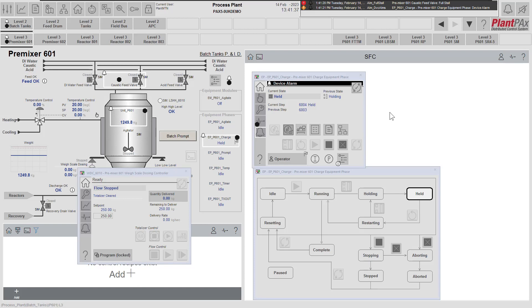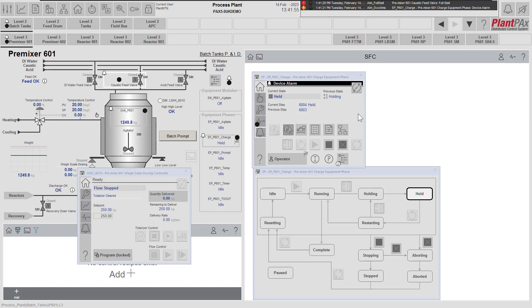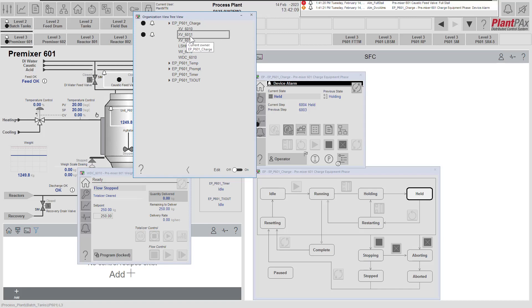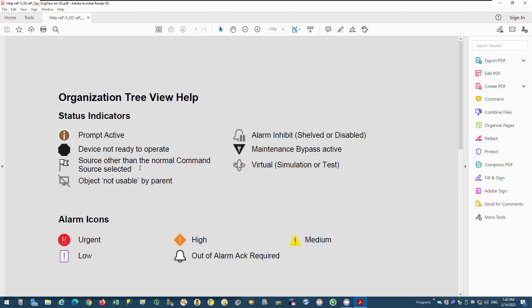It may not be immediately obvious to the user of the equipment phase why it has gone into hold and what's going on. The organization ownership and arbitration framework that the equipment phase uses makes it very easy for the user to now understand what's going on. We start by bringing up the organizational view from the equipment phase, and we can now see which particular devices have an issue. In our case we can see that it is XV6011, the caustic feed valve. From the help we can understand what the indicators mean — we can see that the device is not ready to operate.